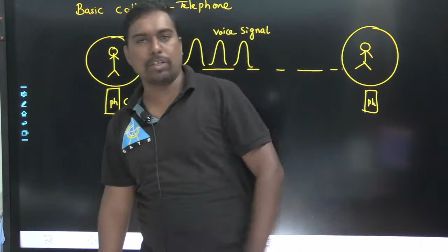If you are sending the signal in the form of voltage, as you know V is equal to I R, each and every wire partition will have certain resistance that will create a voltage drop. And by the time it goes to the end device, like the field sensor to the digital PLC system or analog module of the PLC system, the voltage you get is very, very less. That is why we use 4 to 20 milliamperes.